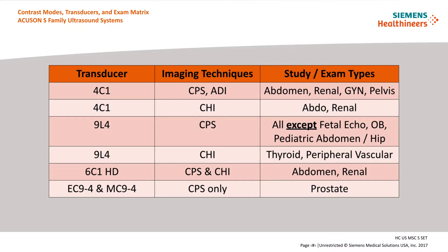This matrix describes which transducers are contrast-enabled along with the associated imaging techniques and exam types. CPS is available on all contrast-enabled transducers, whereas CHI is more selective in the exams it is available on. For example, if a contrast exam is being performed on a superficial region of interest, the user must choose a transducer, exam preset, and imaging technique that best fits the parameters of the exam. If a 9L4 transducer and CHI imaging technique are required, the available exam types are thyroid and peripheral vascular. CHI will not be available with the 9L4 transducer if a different preset is used. This exam matrix is available in the system user manual.